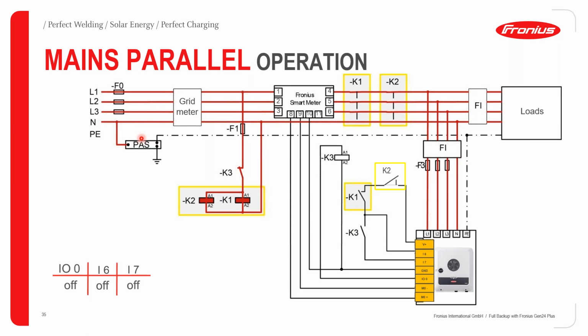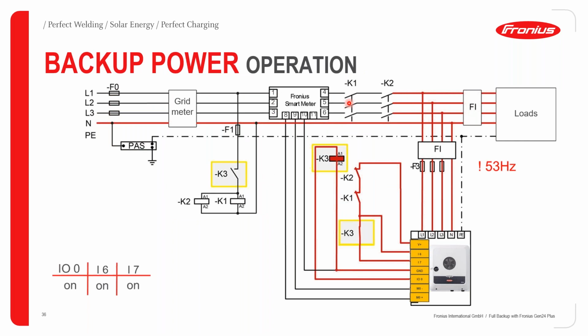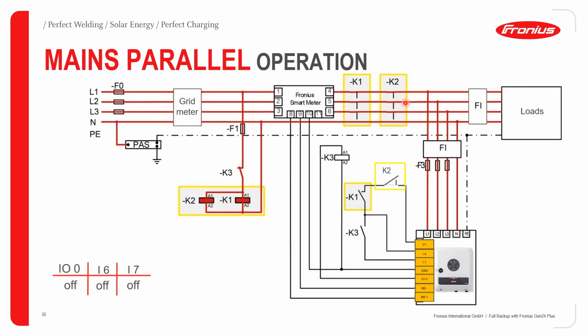So let's take the case where we have grid present and we have connected our backup switch, or full backup disconnection switch. This is how the orientation looks. Once there is a power outage, this is what happens, because the backup switch engages and disconnects the load from the grid, as you can see in this case. Let me go one step backward for you to see how it was. So there is a connection to the load via the contactors K1 and K2.